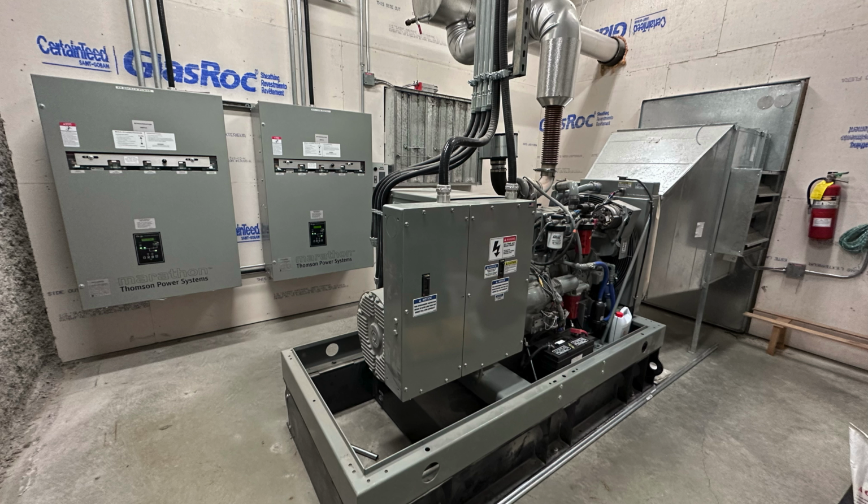So what is this load bank exactly? Well, it basically applies a resistive load to this generator to be able to test it at a very high current. Basically it's a bunch of heaters with a fan, just a big old resistive load, with fans that blow air through it to keep it cool. It's basically a giant heater. Anyways guys, that's enough storytelling, let's get into the video.